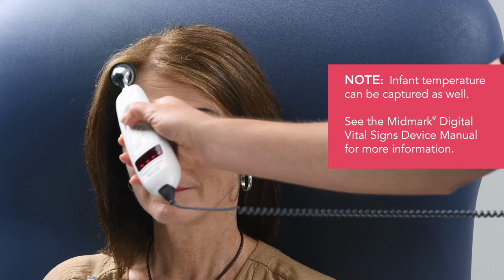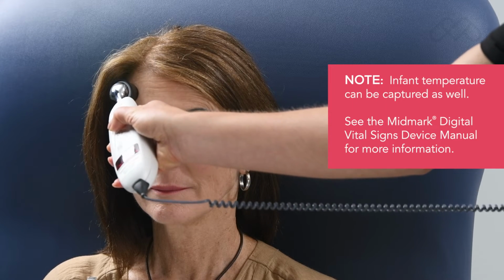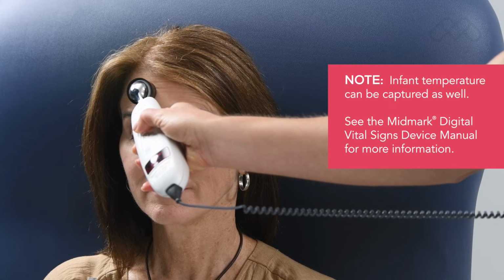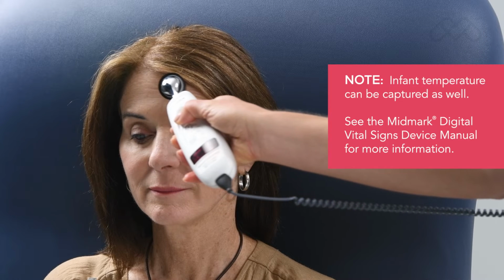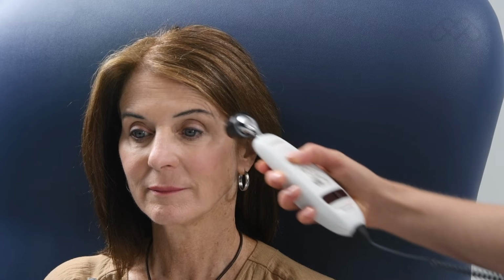For adult temperature measurement, place the probe flush on the center of the forehead and depress the button. Keeping the button depressed, slowly slide the probe midline across the forehead to the hairline. Keeping the button depressed, lift the probe from the forehead. Touch behind the ear halfway down the mastoid process and slide down to the soft depression behind the earlobe. Release the button, remove from the head, and read.